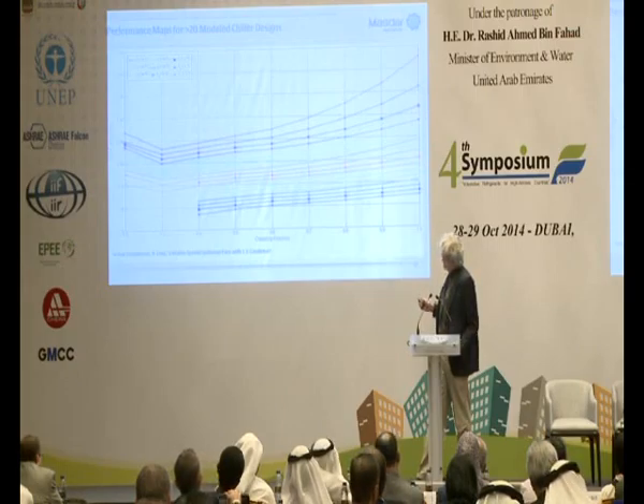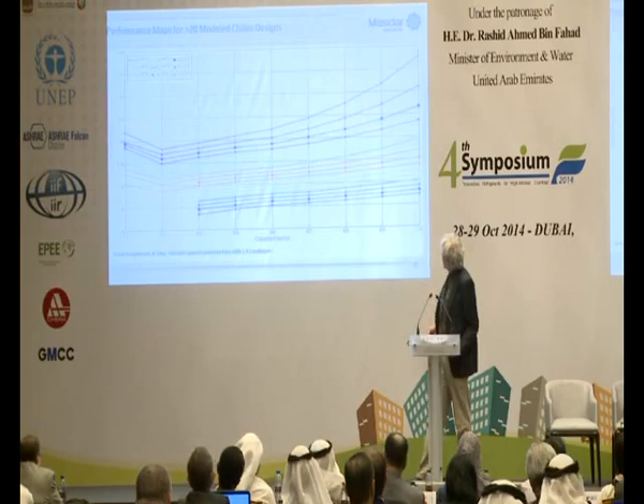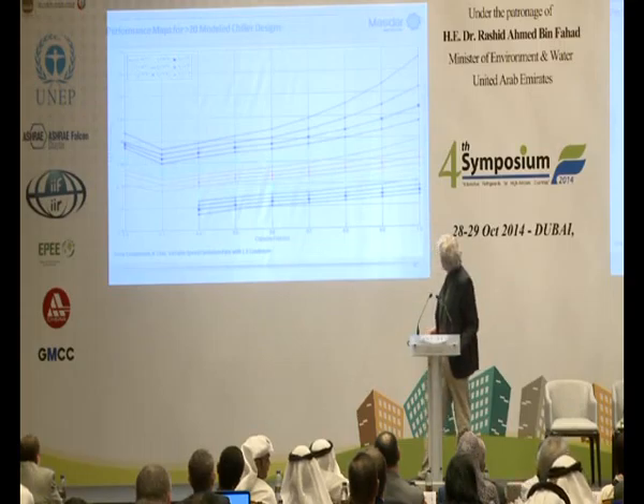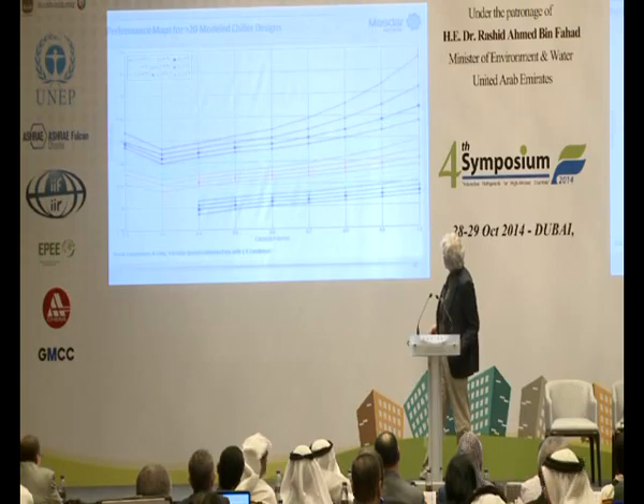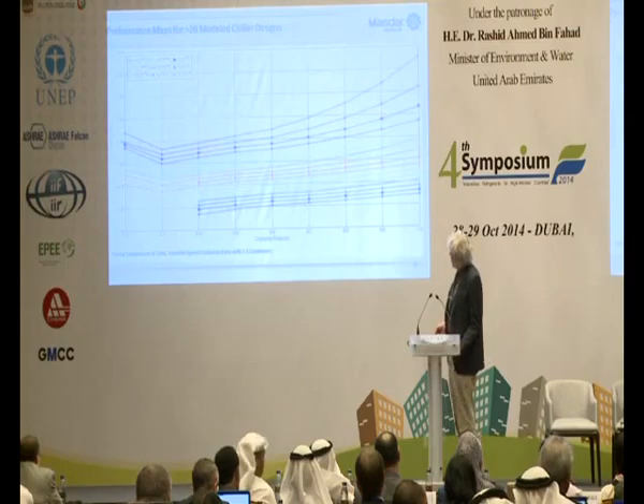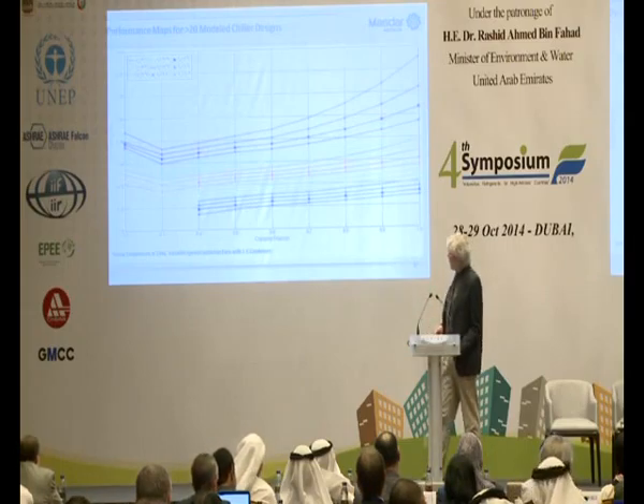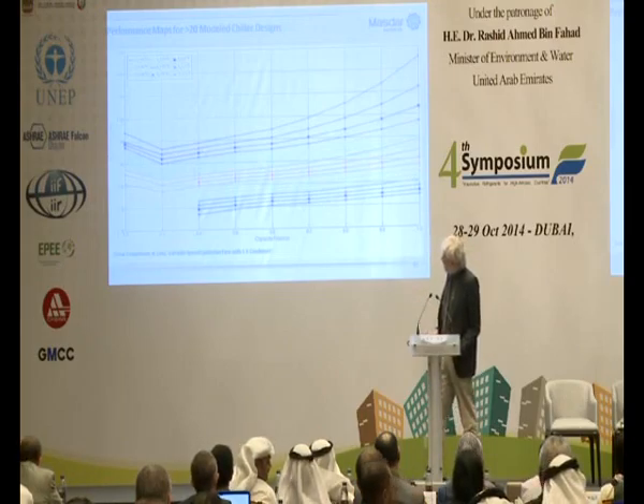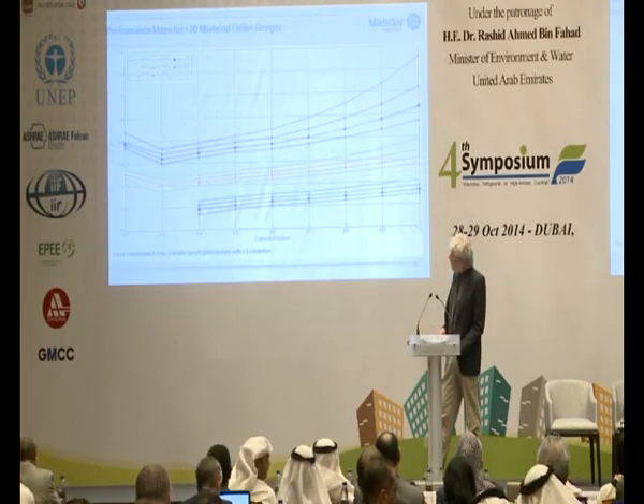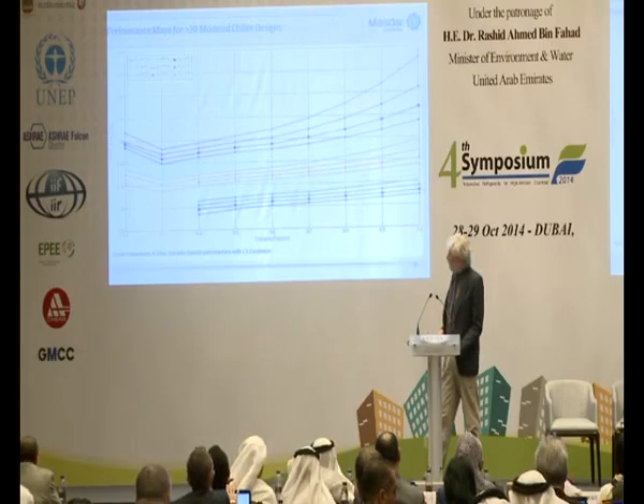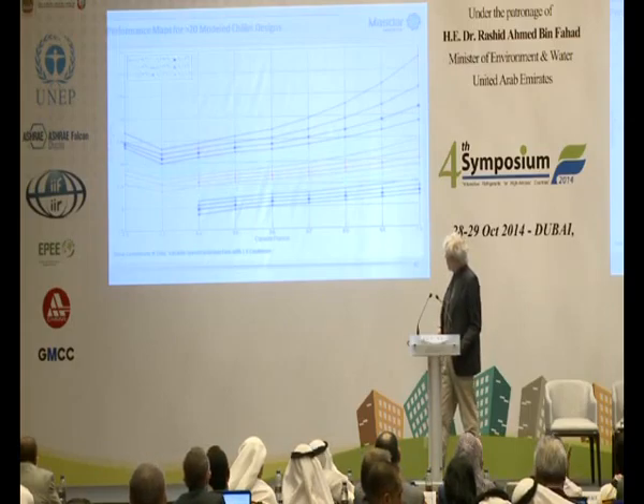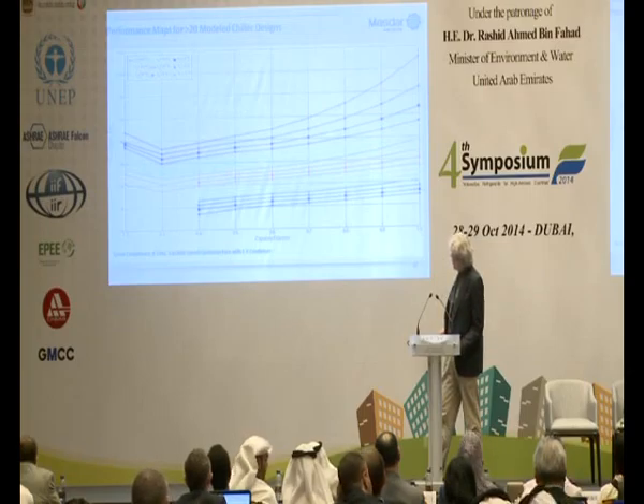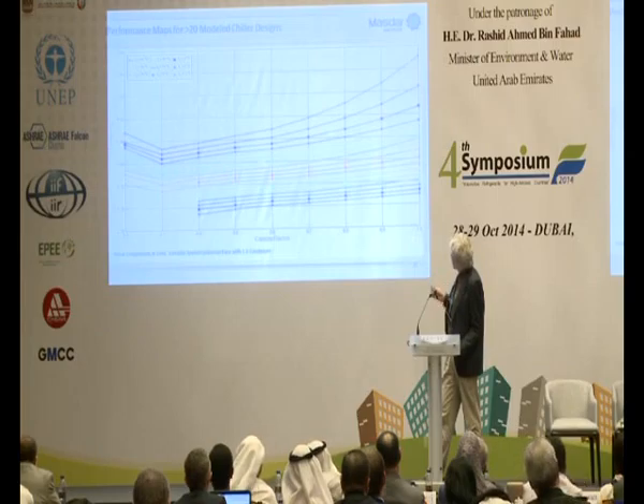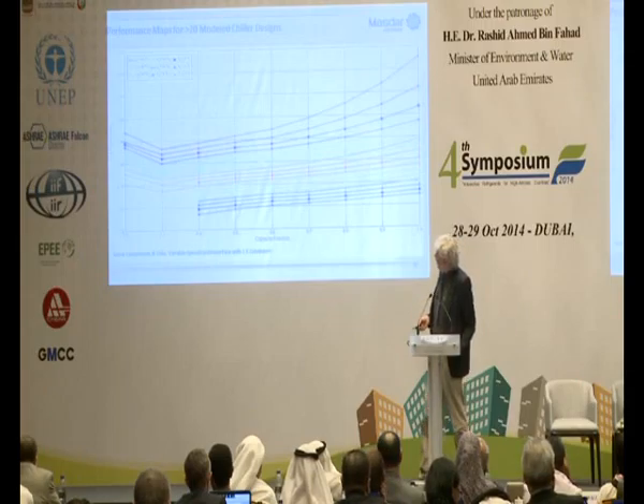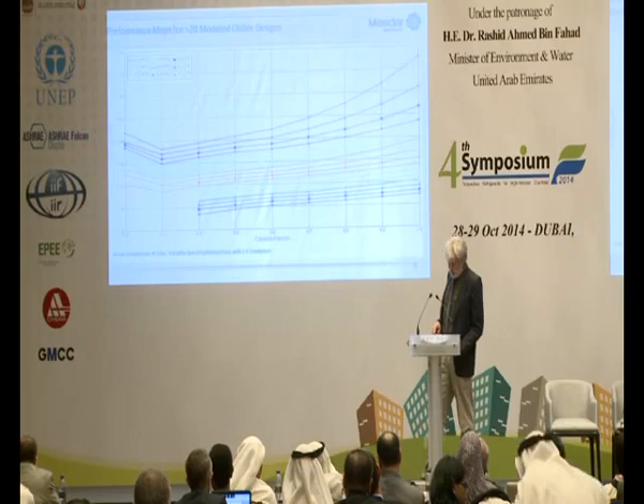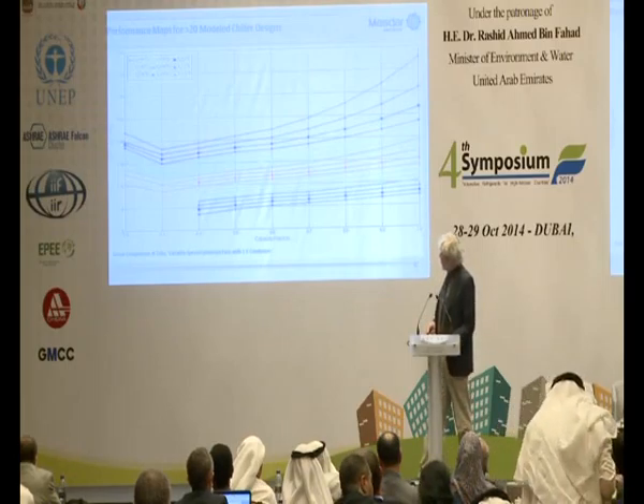So just very quickly, here's the magenta for 45 C. The cyan is for, I can't remember, 40. Red is 35. Green is 30, and blue is 25. So we see the specific power, as you expect, rises with capacity fraction with a variable speed compressor, starting from a rather low capacity fraction of about 0.3. But below 0.3, again, performance starts to drop because we have a certain overhead with the inverter and some of the flow back leakage losses in the compressor. And of course, the specific power increases rapidly with pressure ratio, so for the higher ambient temperatures. So we have, I think, 4 by 5, 160 points here, to which we fit a modified tricubic equation.